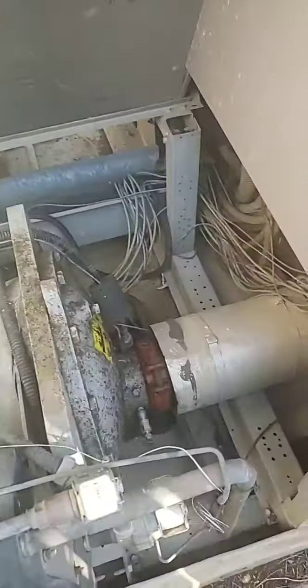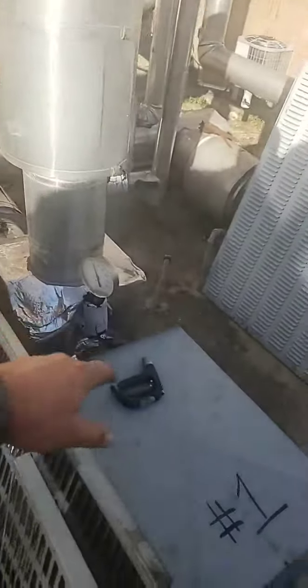Anyway, so that's your basic operation on the compressor side of things. Your screw compressor, your economizer, your liquid line, your cooling circuits, your EXV, your evaporator. Like I said, water inlet coming in, and then you've got your water outlet going back out to the building. We'll step around here. I've got all these panels off, but you can see your pumps here. These are all water pumps. Now, these pumps are actually controlled by the chiller itself. So the chiller has a relay inside of it that's triggering the pumps to bring them on.